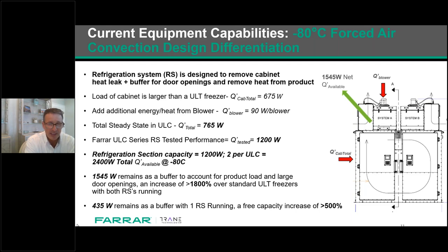So when you take the total reserve energy capable from this ULC, that's approximately 1,800% over a standard ULT freezer. And again, that's with both refrigeration systems running. Keep in mind, 435 watts remain as a buffer with one refrigeration system running, which gives you what we call a free refrigeration capacity increase to over 500% over a ULT freezer. Next slide, please.